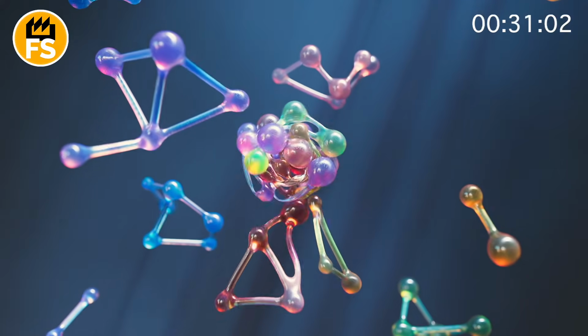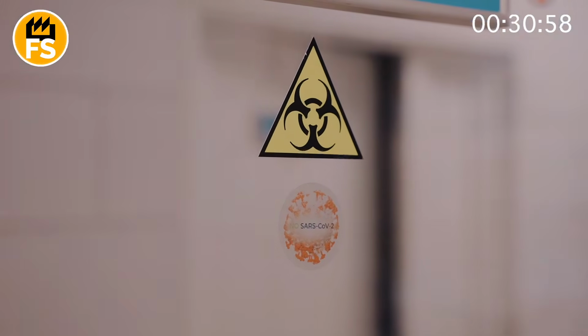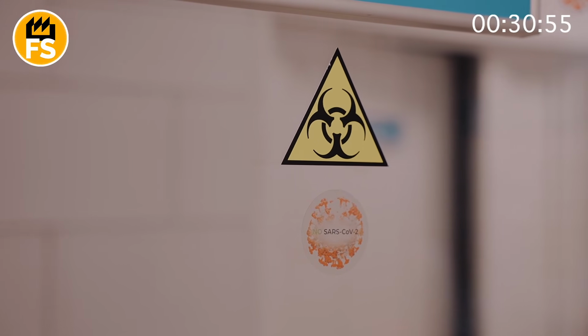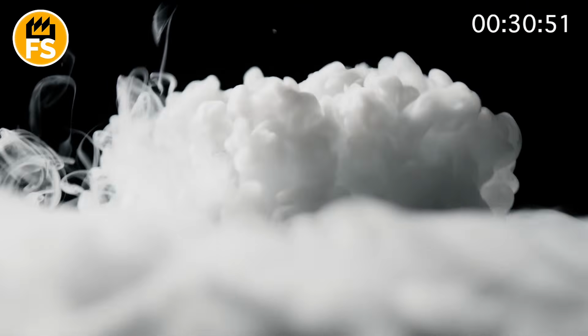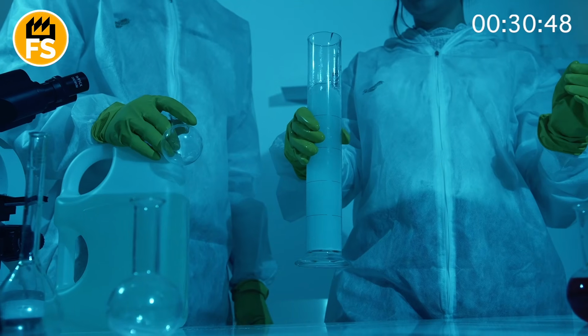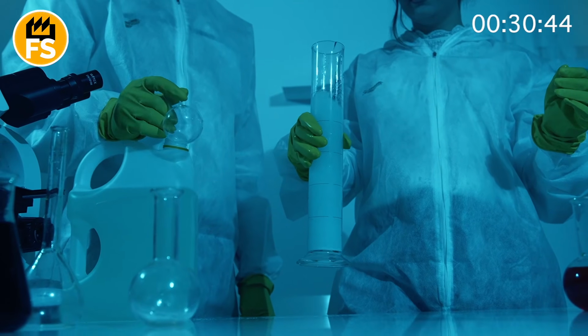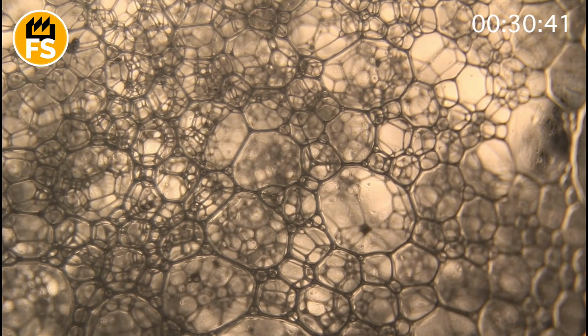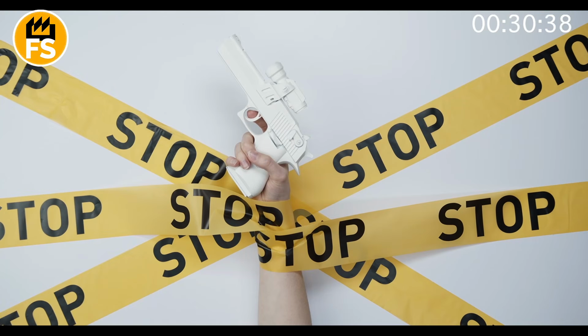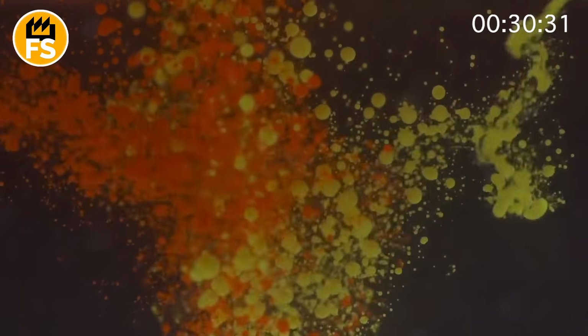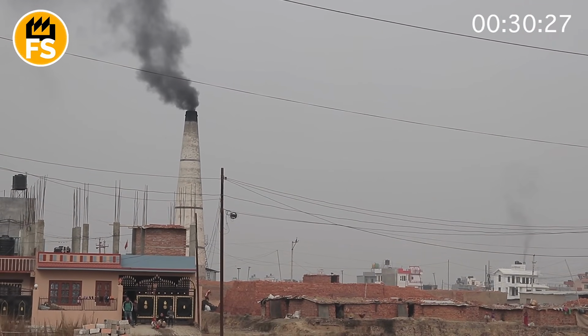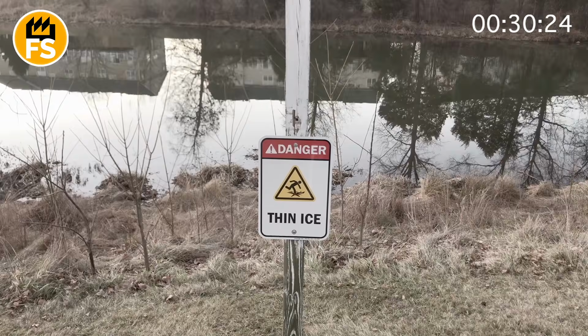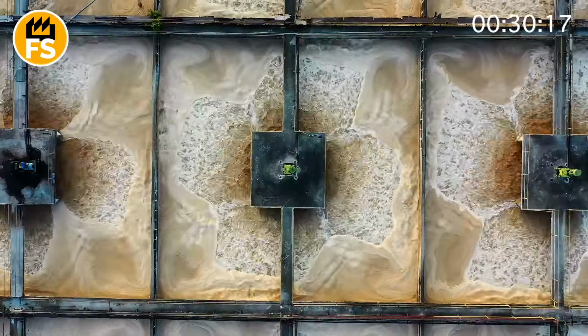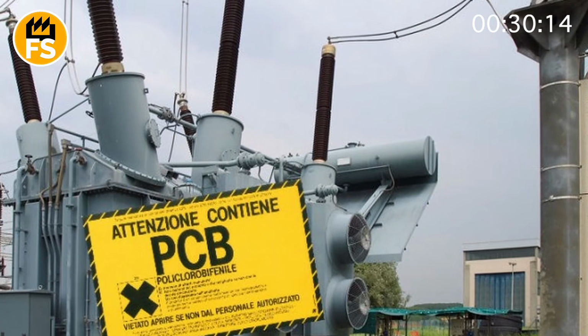Handling and disposing of this hazardous solid waste requires extreme care and strict protocols. The safely drained PCB oil, the contaminated solid materials, and even the specialized protective gear worn by workers after handling these substances must be meticulously contained, documented, and transported for disposal according to stringent environmental regulations. This often involves complex logistics chains, moving the waste to highly specialized hazardous waste landfills designed to permanently isolate the toxins, or to permitted high-temperature incinerators, specifically designed and certified to safely destroy PCBs at extreme temperatures. It's a costly, complex, and highly regulated part of the process, a hidden necessary step ensuring those dangerous chemicals never re-enter the environment to cause harm.